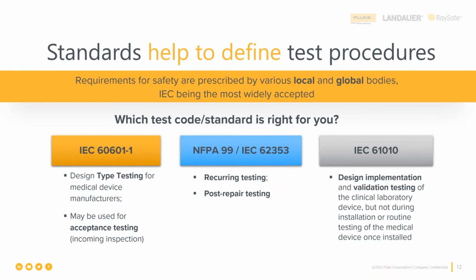So here are the standards underneath the big umbrella called IEC 60601. That is the umbrella. So please, if you're talking about the standards specifically, you need to use the standard's name specifically. Say what you mean, don't shortcut it.